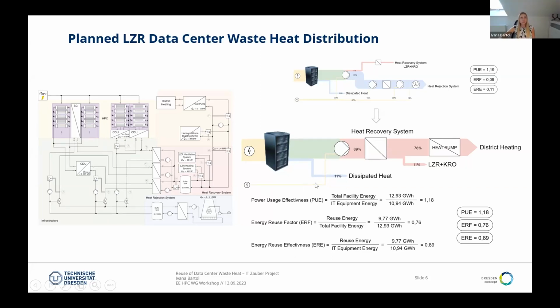This was a big discussion in our project, but according to ISO/IEC 30134, any equipment whose purpose is enhancement of waste heat shouldn't be accounted in the key performance indicators of this data center. So there is considerable power consumption from this heat pump, but it should not be part of the PUE of the data center, because it only enhances waste heat.